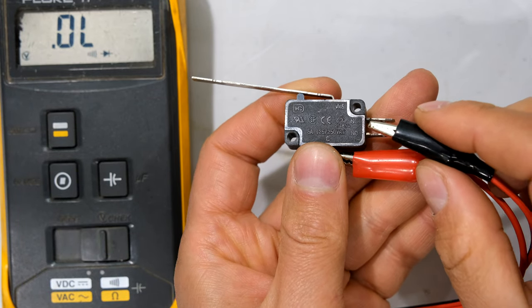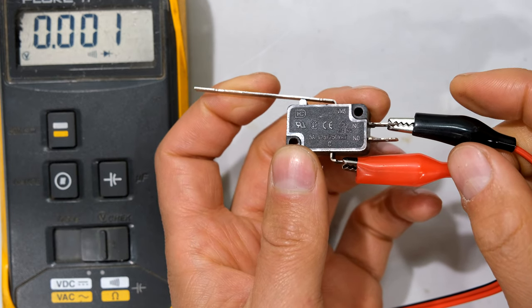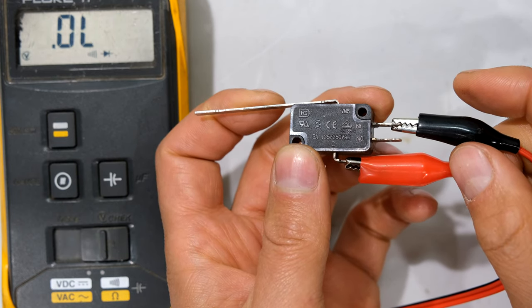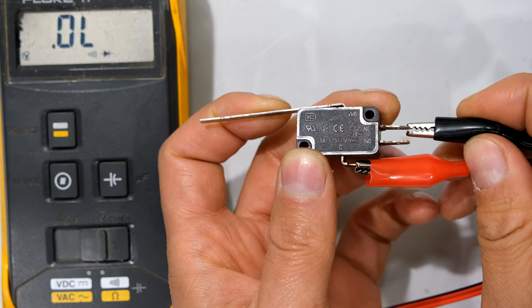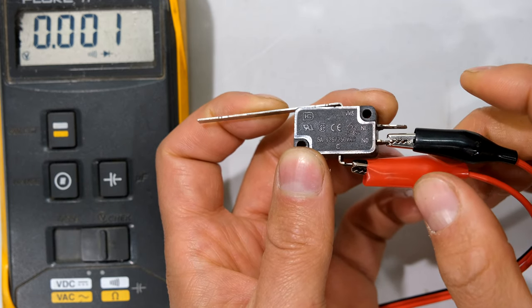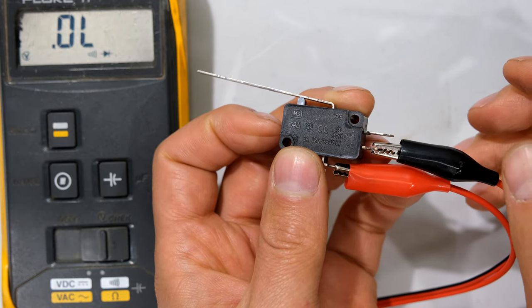Going back to the limit switch, there is one pole and two outputs — two options for how I operate my limit switch. If I connect to the normally closed, the circuit is closed and only opens when the lever is depressed. If I connect to the normally open terminal, it becomes a closed circuit only when the lever is depressed.